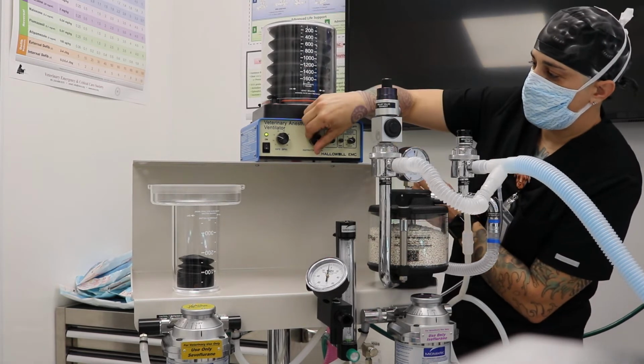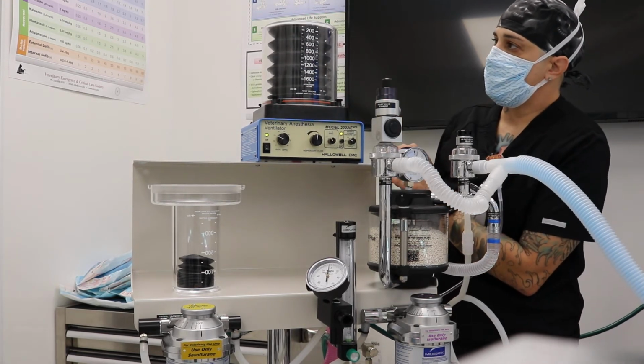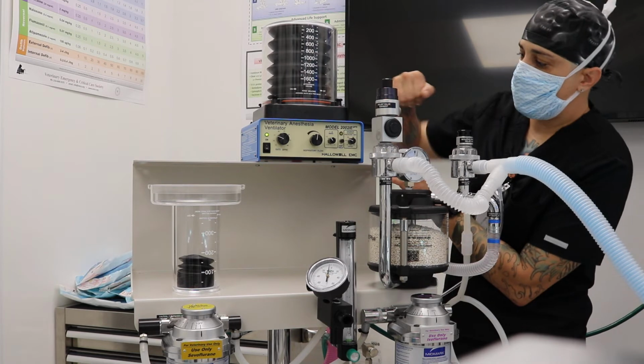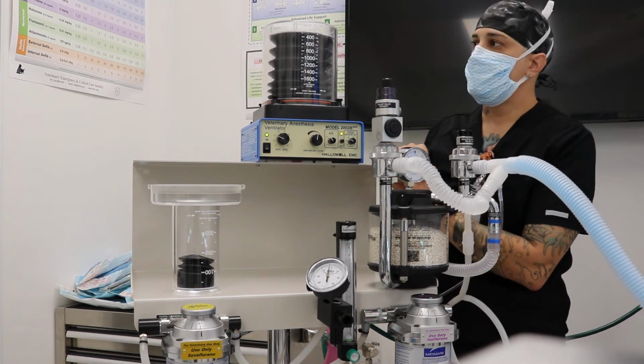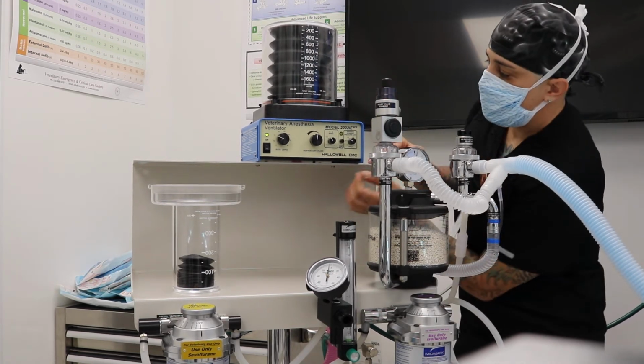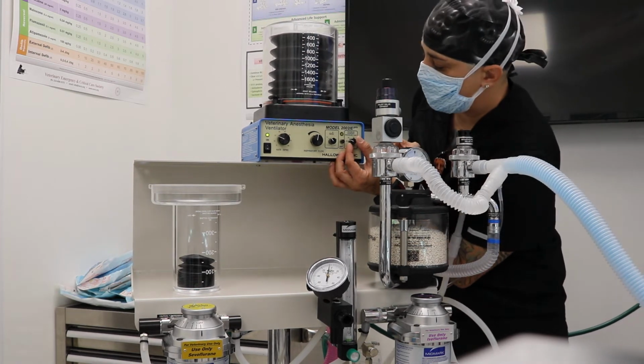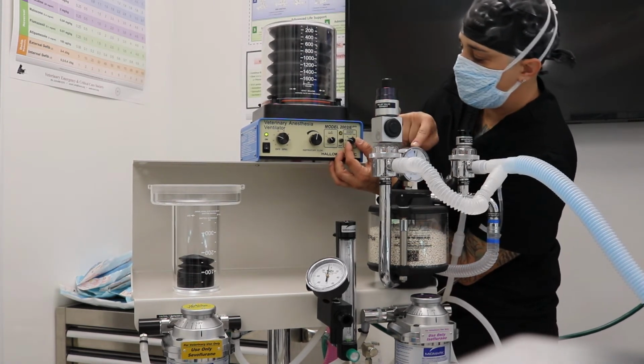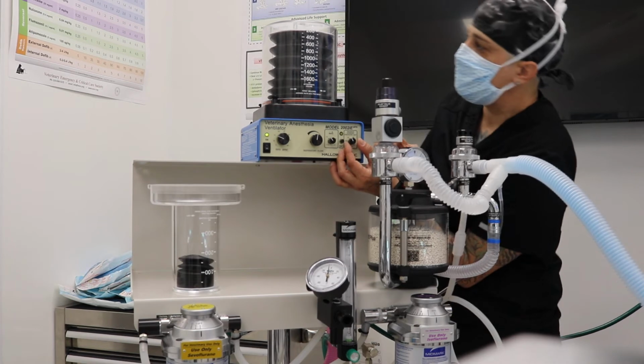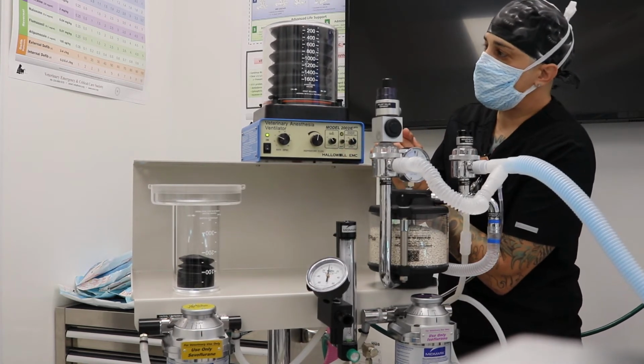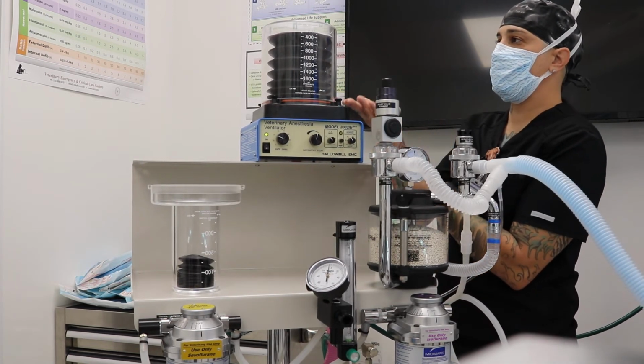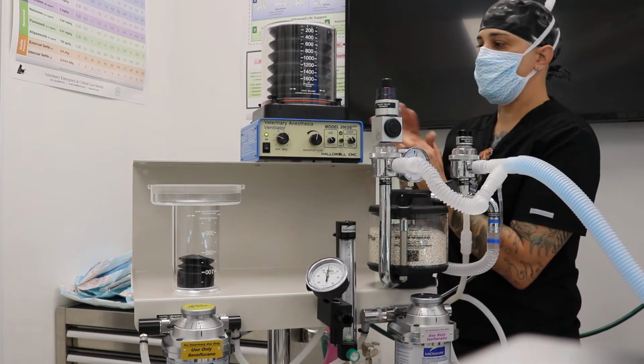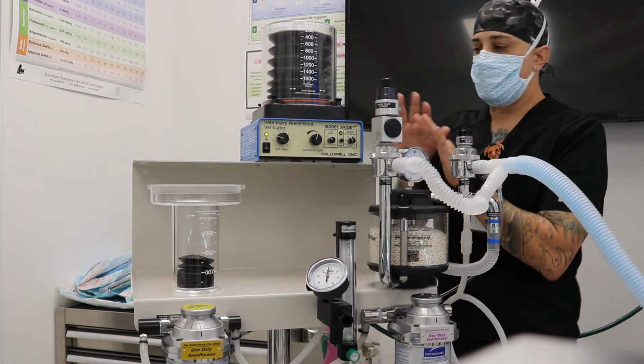Good. I'm going to give a little bit more volume. That's telling me that I'm going over my 20 centimeters of water. As for right now, I'm doing a leak check. I'm okay with that. I'm going to move my maximum working pressure limit, which correlates to my positive inspiratory pressure, up to 30, just for a leak check only. So it looks like we're good. The bellow is going all the way back up to the top. It's not dropping at all. So we have been leak checked.